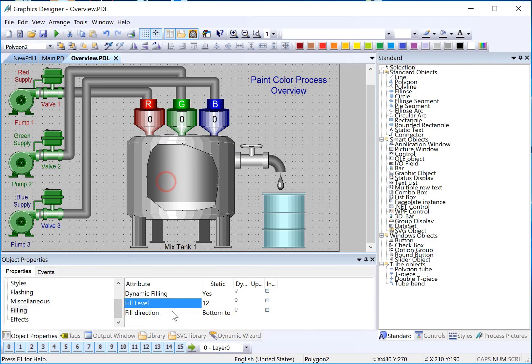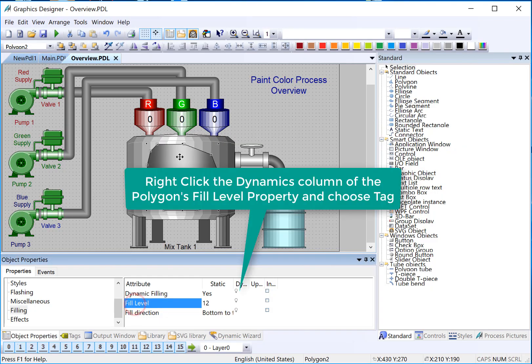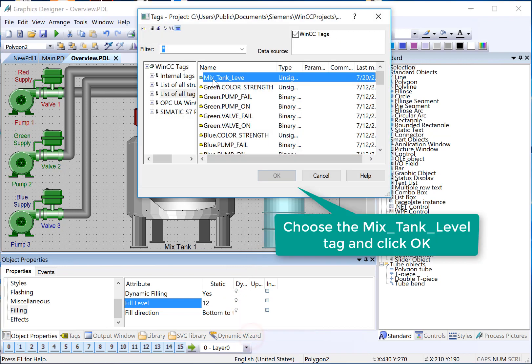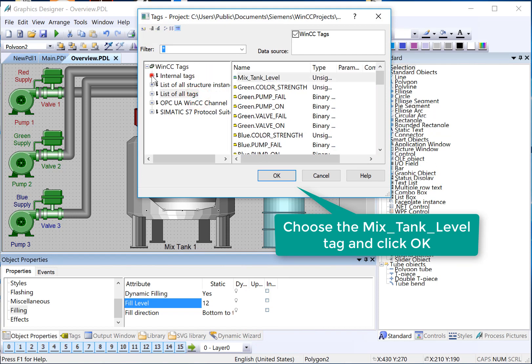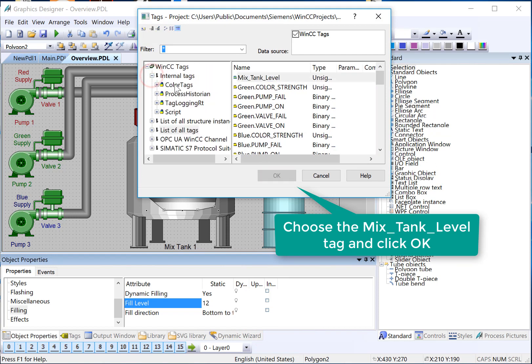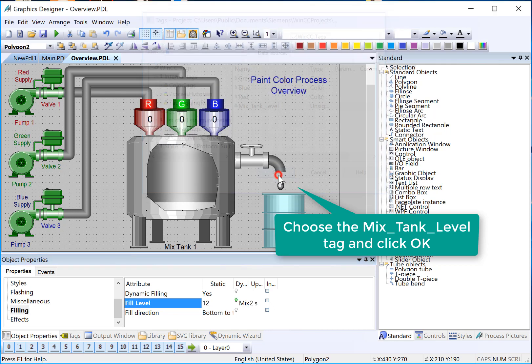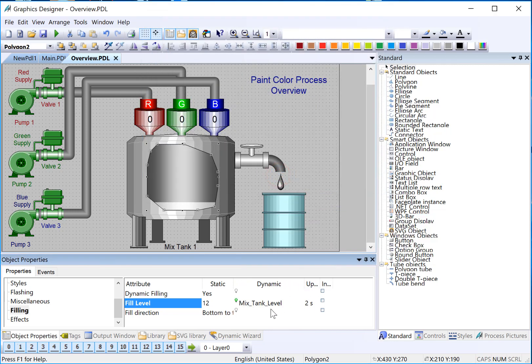Now, back in Graphics Designer, I will go to my Fill Level Objects Fill Level property, right-click under the Dynamic column, choose Tag, and there's my Mix Tank Level that I created. I could also find it by browsing directly here, and I'll just click OK. Now, any value that's in this tag is going to be translated into a tank level. So let's use the WinCC Tag Simulator to see what that looks like.